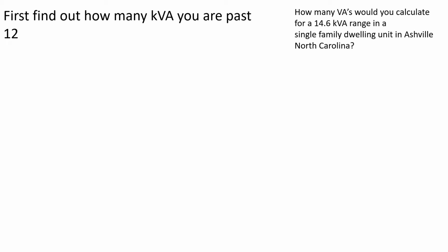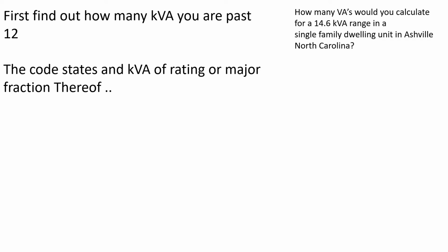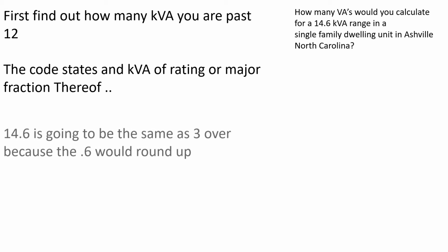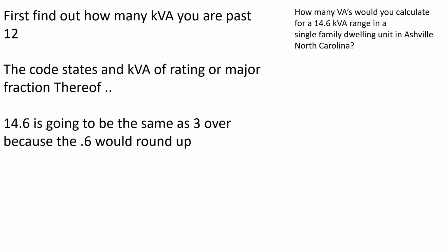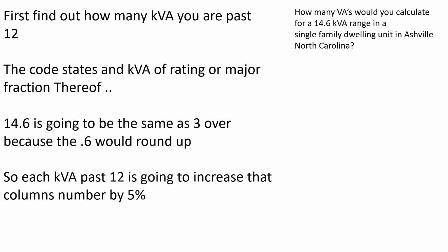Okay, so first you have to find out how many kVA you are past 12. It's saying that you must increase it for each kVA past 12 by 5%. The code states that it's a kVA or major fraction thereof, just like in multi-outlet assemblies. So if it's 0.5 or past, it's going to count as another kVA. 14.6 is going to be the same as 3 because the 0.6 would be rounded up. So we are 3 kVA past 12. For each one past 12, we're going to increase that column's number by 5%.